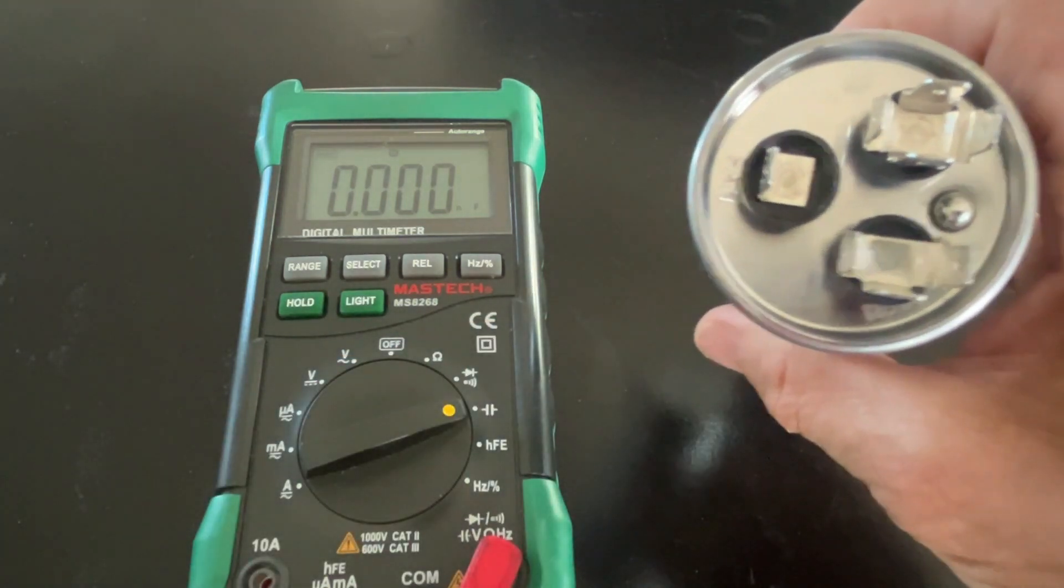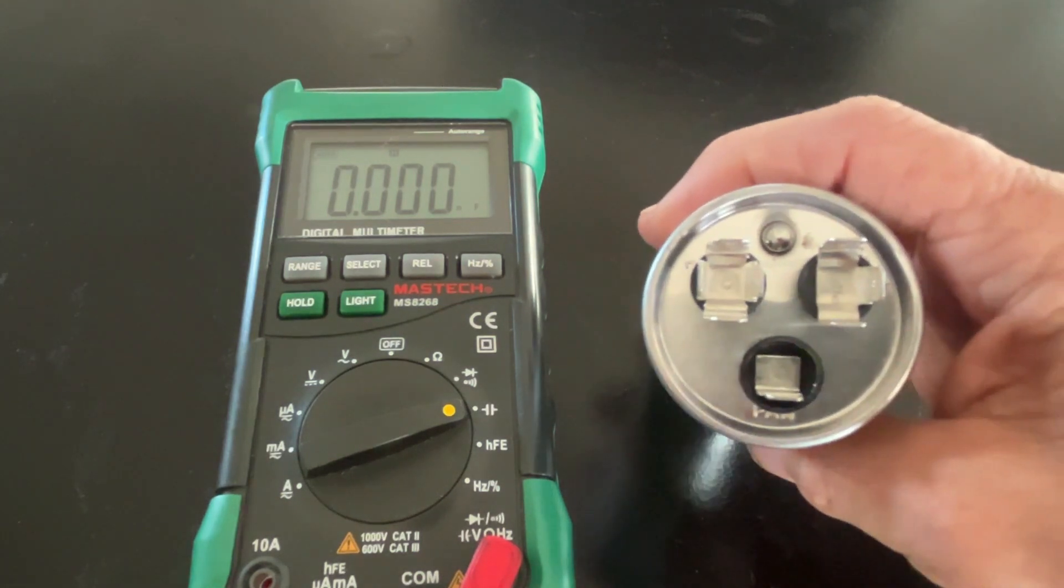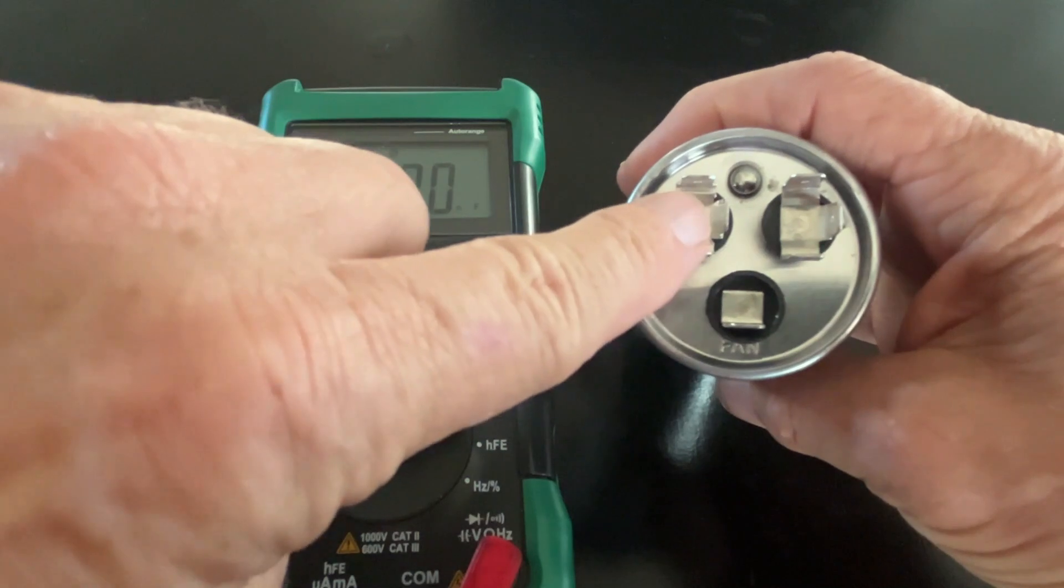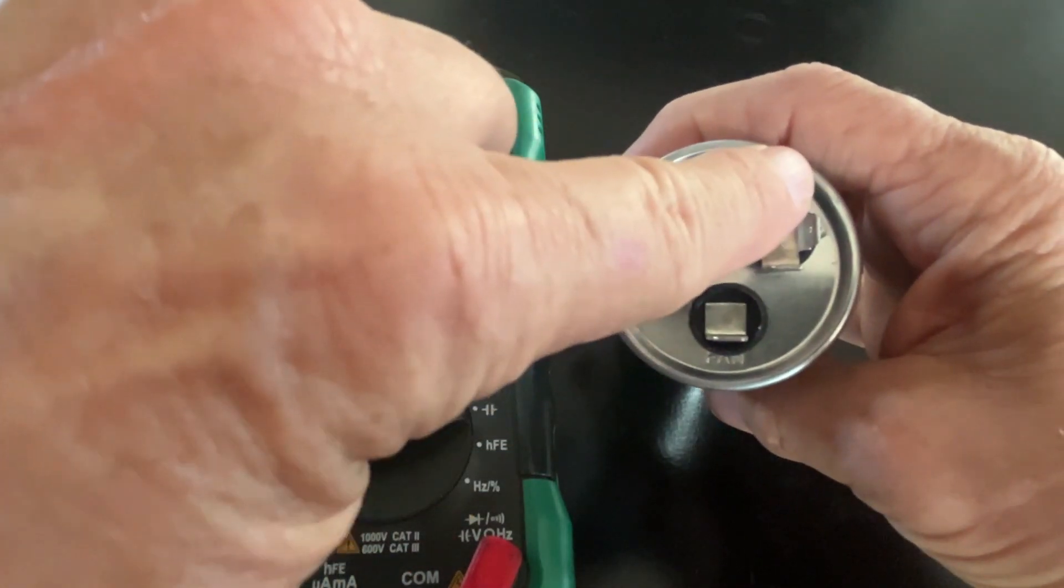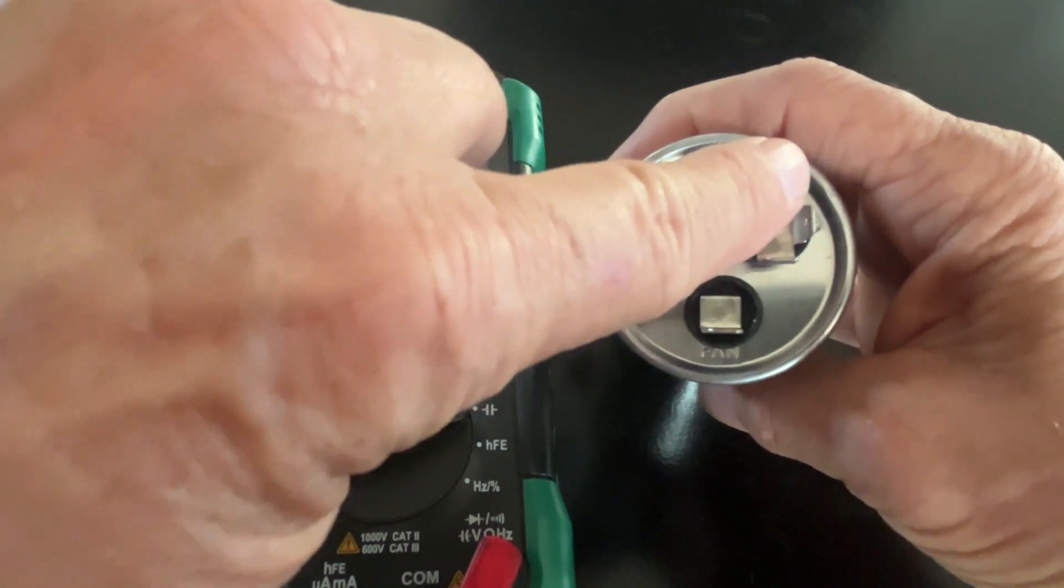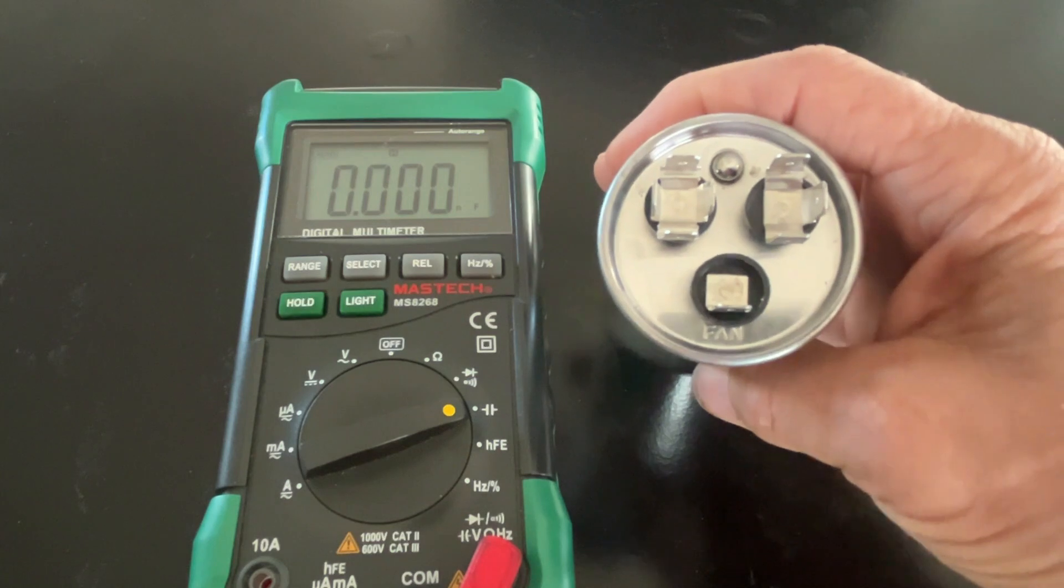Here's the C, so this is the common, this is the fan, and this says HERM, which stands for hermetic compressor. To measure or test this, you're going to measure from the common to the fan and from the common to the HERM. The HERM is going to be the higher value, so that should be 45, and from the common to the fan should read close to 5 microfarads.